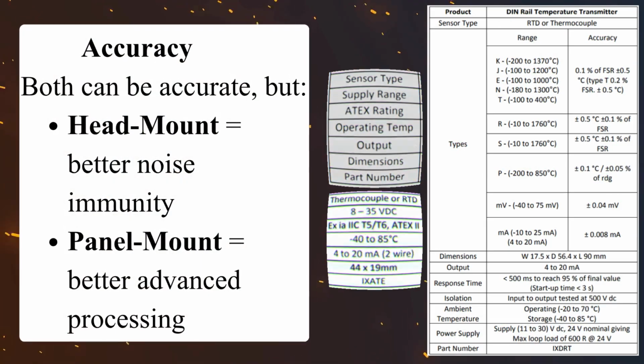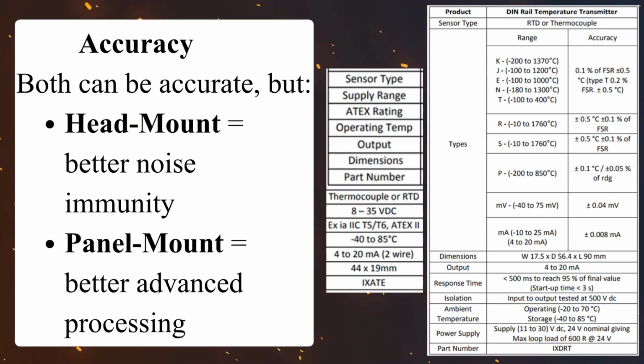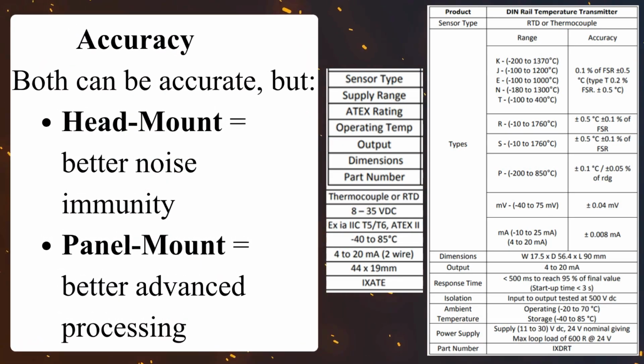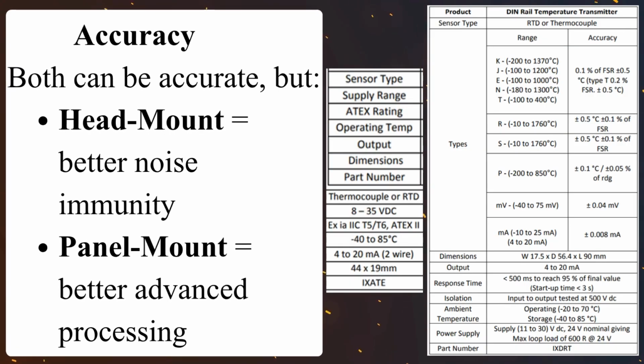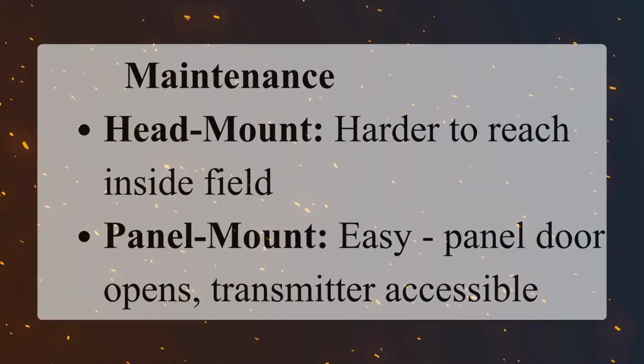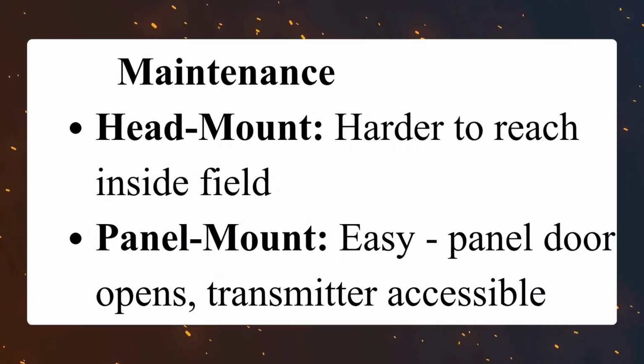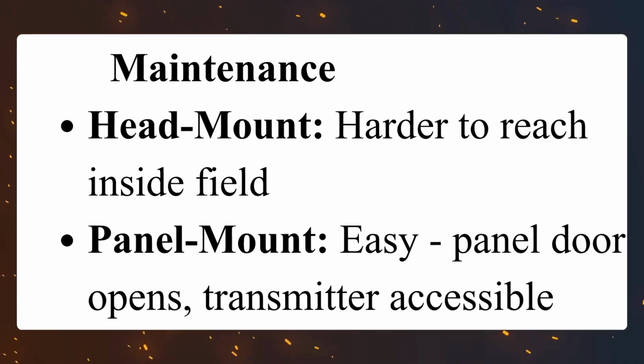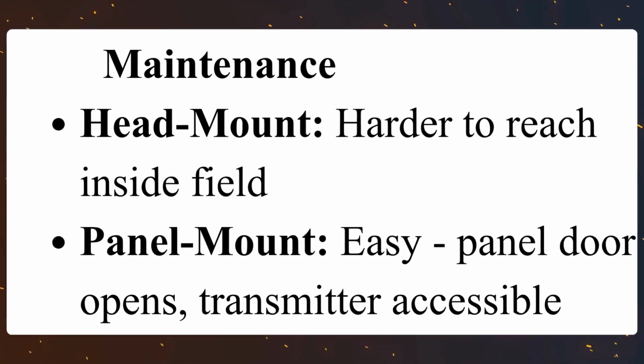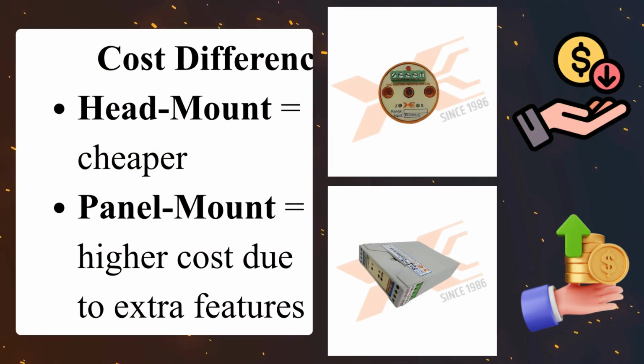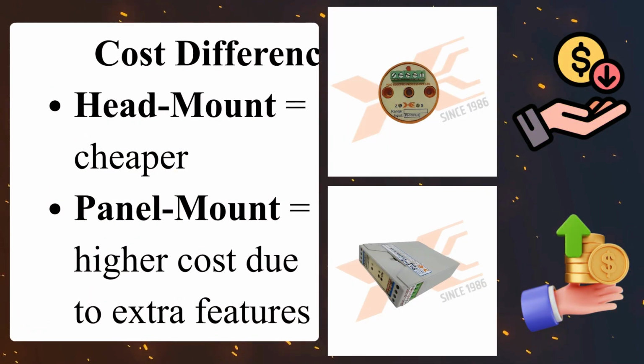5. Accuracy. Both can be accurate, but head mount equals better noise immunity. Panel mount equals better advanced processing. 6. Maintenance. Head mount: harder to reach inside field. Panel mount: easy, panel door opens, transmitter accessible. 7. Cost difference. Head mount equals cheaper. Panel mount equals higher cost due to extra features.